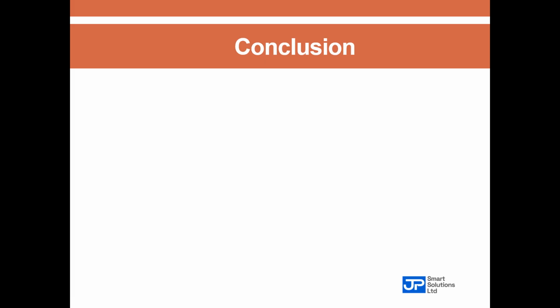Because electrical power systems help engineers cover their errors. Now, you design your protection coordination scheme and all that, and then you implement it in the relays. But then there's no fault for, let's say, the next 3 to 6 months, and then a fault occurs. No one will come and hold you and say, oh, your protection scheme was inadequate, because it worked for a period of 6 months. So it only takes an organization that carries out root cause analysis and very serious interviews to find out what is the actual problem that caused this. So when they realize, oh, you just copied the settings from old projects, and that is the overlap we are having, causing nuisance tripping in our system. So stop copying settings from old projects. Your system deserves a tailored, validated coordination.